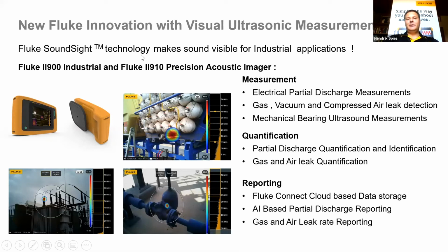And we've got a patented technology called SoundSight, meaning we've got 64 ultrasonic microphones which listen to sound with a high definition video camera, and with a processor in this unit, we can make sound visible. So basically, if you look at these three photos, you'll see on the electrical application here, we can actually detect partial discharge. So we actually make the partial discharge, the electromagnetic wave, we pick it up as sound, and then with the high definition video camera, we can now make the sound visible from the array of microphones displayed on the live image. As you can see, we can do it for electrical assets.